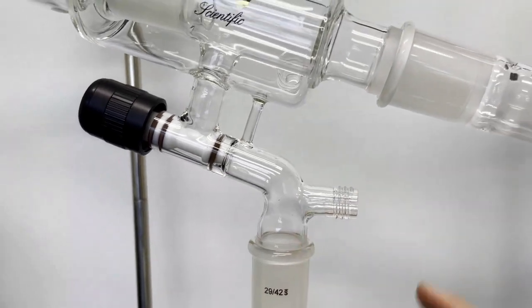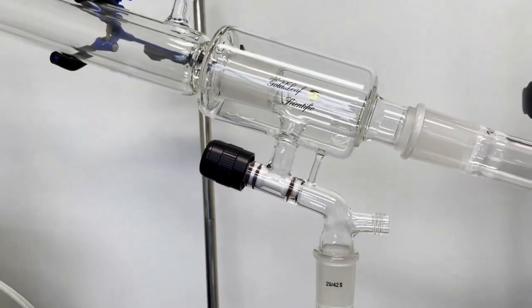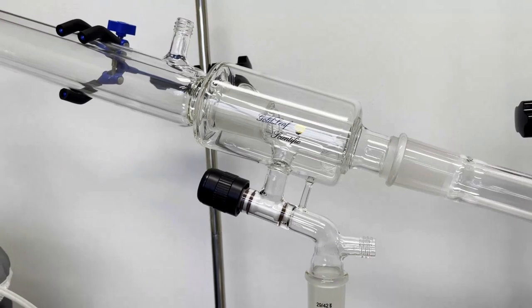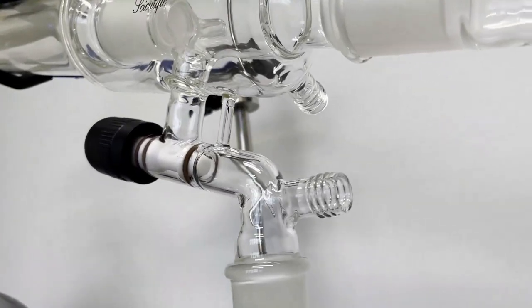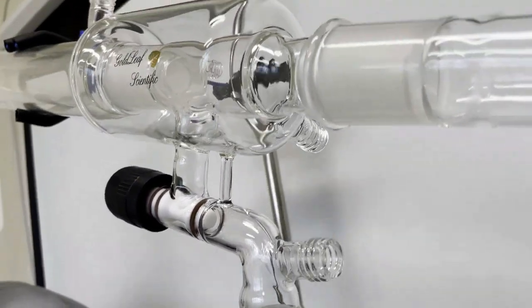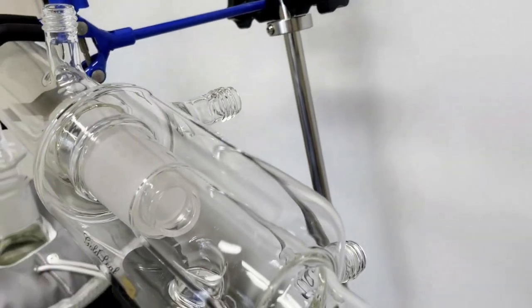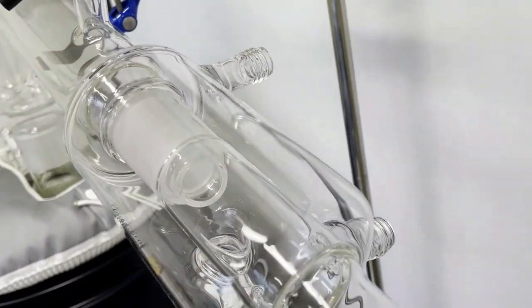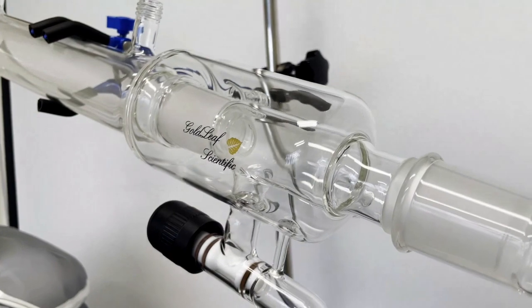This PTFE valve opens and closes to cut off the collection flask from the rest of the system, so the flask can be easily removed and swapped out in the middle of the run without breaking vacuum to the entire system, which would otherwise drastically reduce evaporation rates in the boiling flask by raising the pressure.